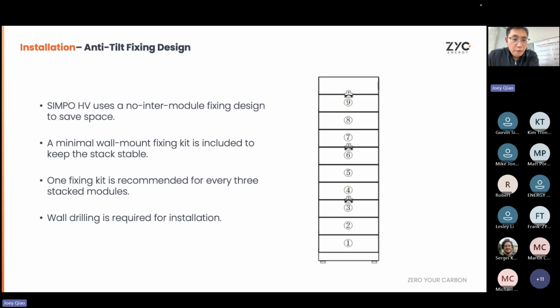Another thing is the fixing. When you install our batteries, we have a bracket on the back side of the battery module to screw to the wall, so you can attach our battery to the wall. Some batteries in the market require a decent distance from the wall, but for our batteries, you can attach them directly to the wall, and make sure to fix the battery modules to the wall. As you can see, every 3 modules we have this bracket for you to fix to the wall to make it stable.